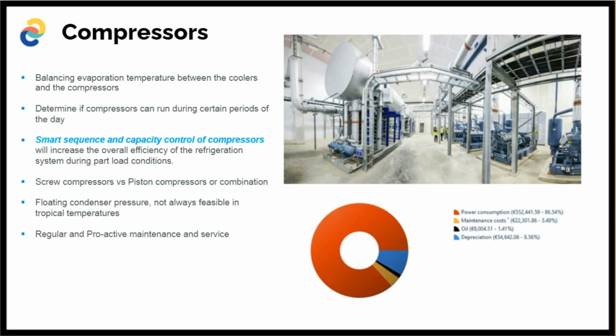Now, what can we do on these compressors? First of all, it's balancing the evaporation temperature between the coolers and the compressors. Do we invest in cheap, smaller coolers, but then we have to bring the evaporation temperature down, and that means bigger compressors. The other way around, if we have big coolers, then we could use smaller compressors. So it's a balancing act.